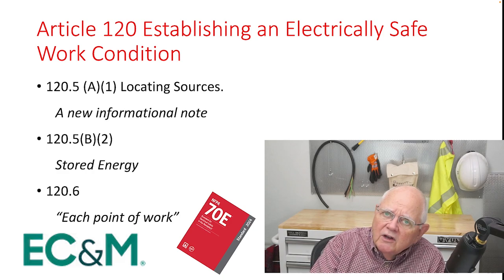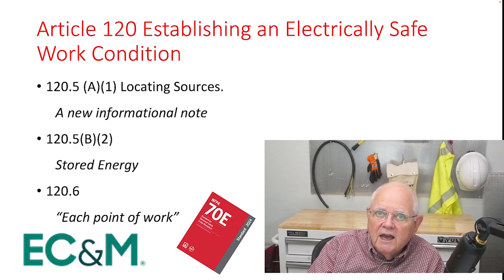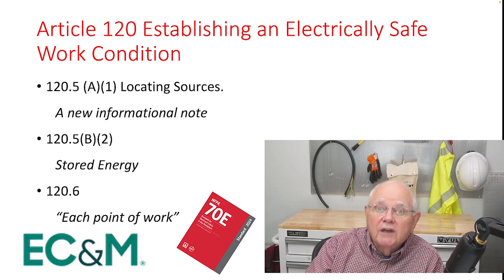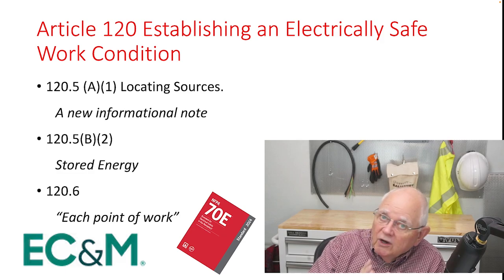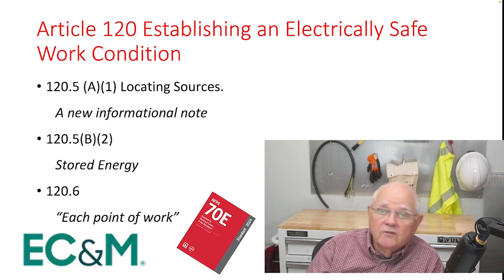But now it also mentions that neutral conductor. And we know, depending on how our circuit is laid out, that even though we open up the breaker, de-energizing the ungrounded hot conductors going to our load, we can still have current flow through that neutral conductor. It still can be a current-carrying conductor carrying current flow from other parts of a circuit. So it's just giving us that informational note to make sure that we're aware of that.